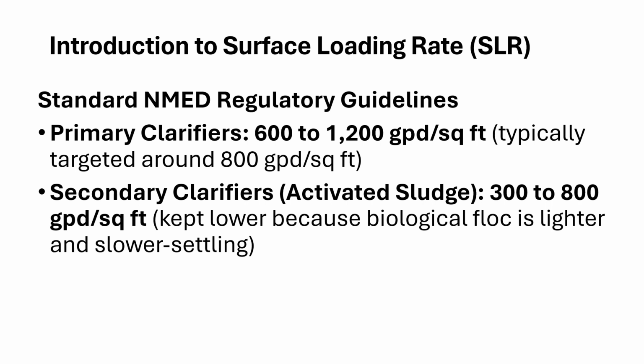They're quite delicate, and we want to make sure that any wastewater moving through this process is moving fairly slower because these floc settle out much slower. So we don't want to disturb those. We want this floc to settle out to the sludge blanket. So that's why a secondary clarifier's surface loading rate is much slower than a primary clarifier surface loading rate.